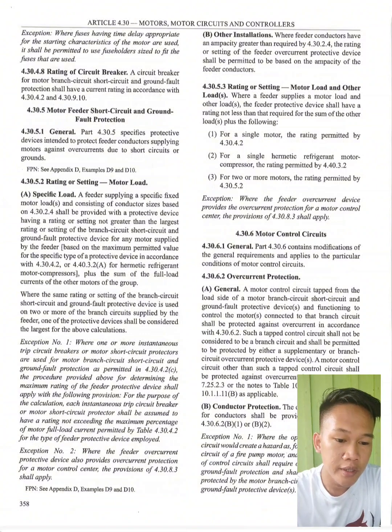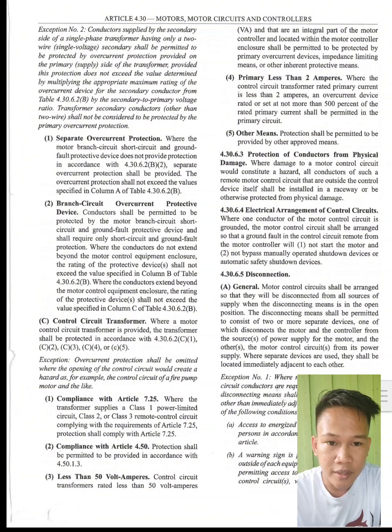We have the first exception: where the opening of the control circuit would create a hazard, as for example the control circuit of a fire pump motor and the like, conductors of a control circuit shall require only short circuit and ground fault protection and shall be permitted to be protected by the motor branch circuit, short circuit, and ground fault protective devices. So we have the second exception.